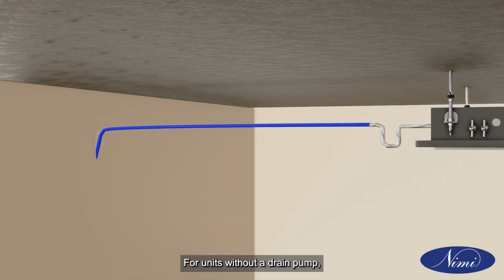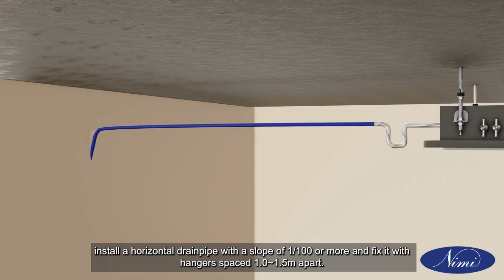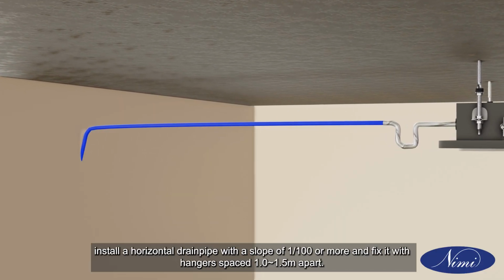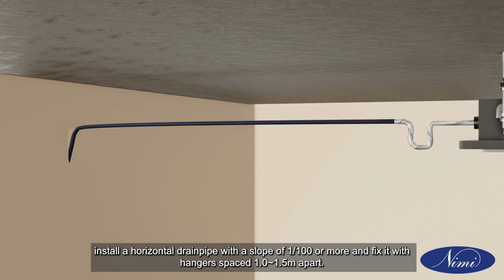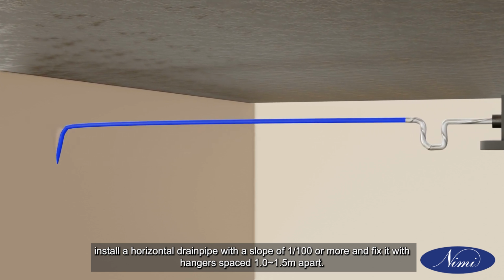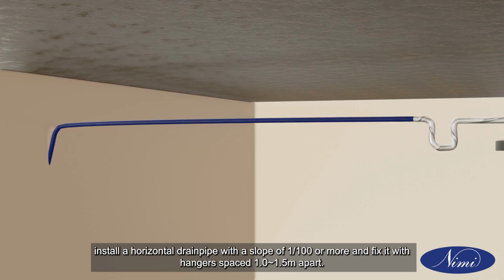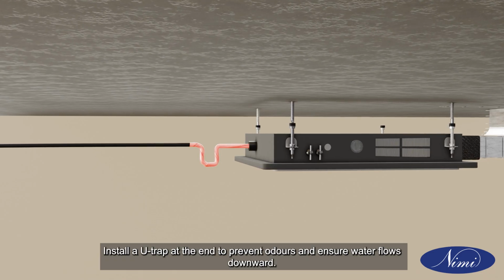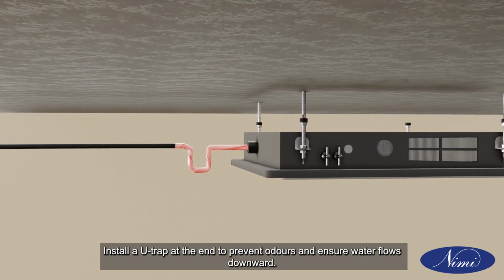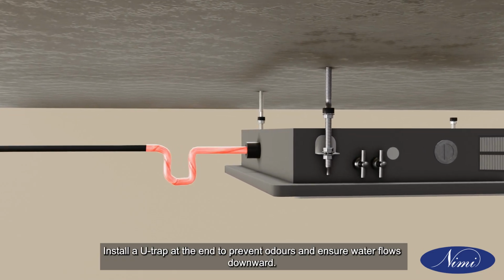For units without a drain pump, install a horizontal drain pipe with a slope of 1/100 or more and fix it with hangers spaced approximately 1.0 to 1.5 meters apart. Install a U-trap at the end to prevent odors and ensure water flows downward.